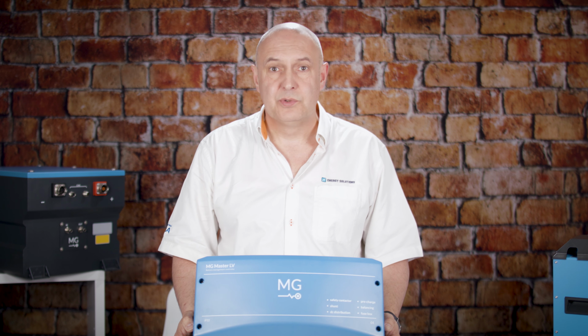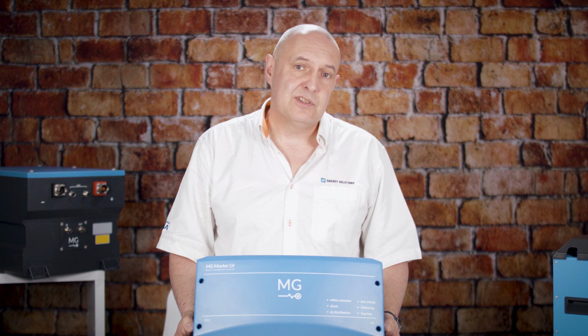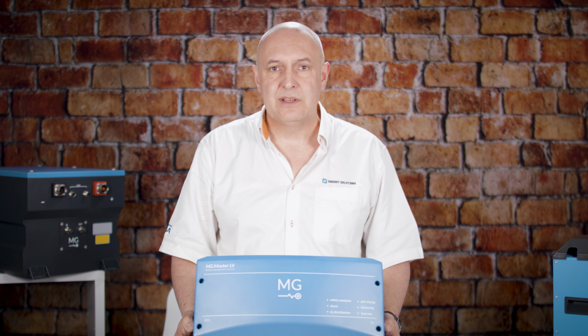Within the BMS is a protection contactor, and this is there principally to protect the battery against overcharge or over discharge. It is able also to be used as your main isolation for your system on board, so you can control it manually as well. There are various models of the BMS with different capacities of contactor built into it, ranging all the way up to 1000 amps.